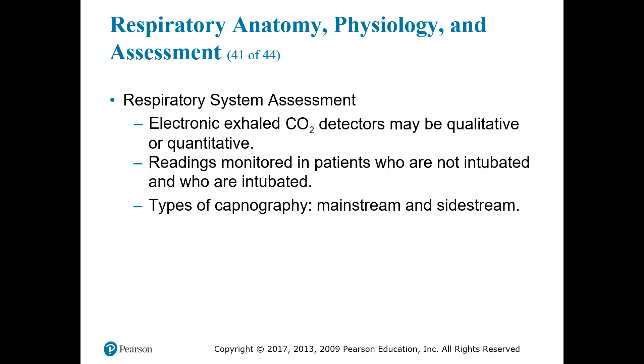As we continue talking about end-tidal CO2, our electronic exhaled CO2 detectors may be qualitative and/or quantitative. Qualitative means they're going to either give us a yes or no answer — either yes, there is CO2 present, or no, there is not. Quantitative is going to give us a number associated with that; it tells us if CO2 is present and also gives us the actual number we are looking for.